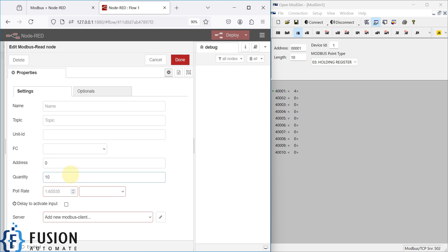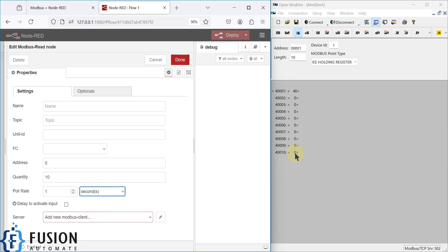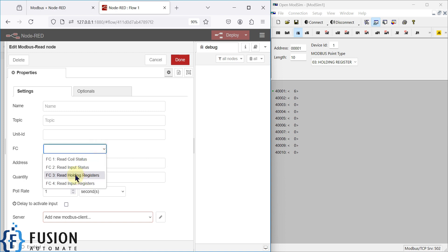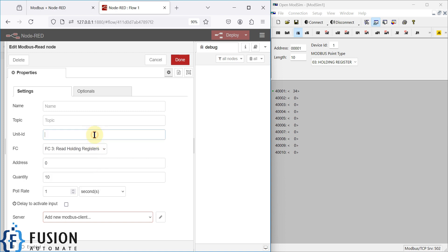The poll rate is set to one second, so data will be read at an interval of one second. The register type is set to holding register, and the unit ID is set to 1. This completes the basic read configuration for the Modbus Read node.